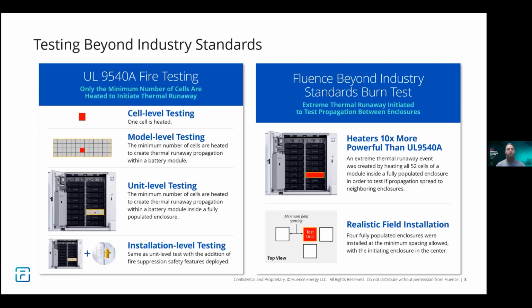Fluence goes through our UL 9540A testing just like everybody else, and we've been very successful with it thus far. In addition, we've taken it one step further with Fluence's beyond-industry-standards burn testing. This is a custom test where we took the heaters and ramped them up by 10 — the power of our heaters was 10 times greater than what was utilized in the UL 9540A test — and instead of pushing a single cell into thermal runaway, we pushed 52 cells into thermal runaway.